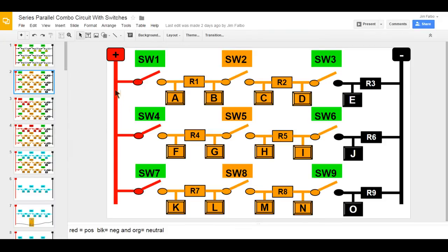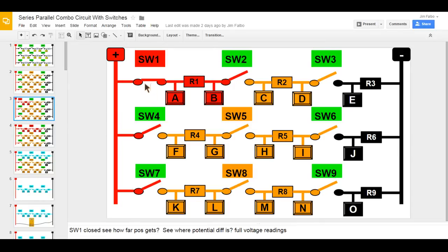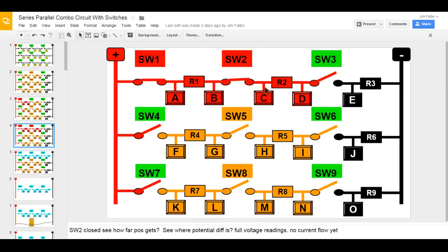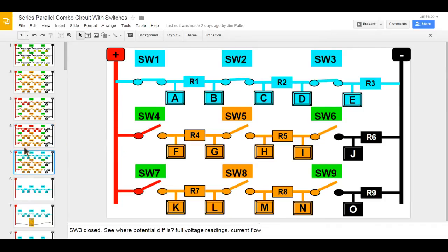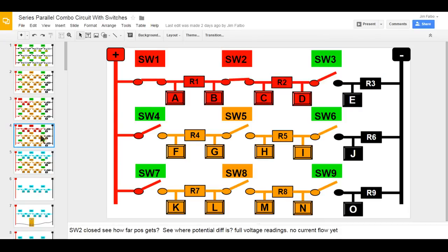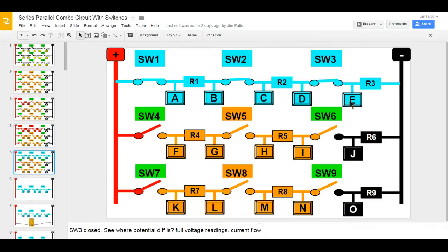If I take a voltage reading where I have red and black I would see full voltage. I've closed switch one and everything is normal — the positive makes it up to test point B. A reading from A to B would be zero because it's the same color, but Bravo to Echo I would get full voltage. Closing switch two continues positive flow, and closing switch three — when it's open, you get full voltage drop across it; when closed, voltage spreads out. The sum of voltage drops must equal supply voltage. This is rung 1, rung 2, and rung 3.